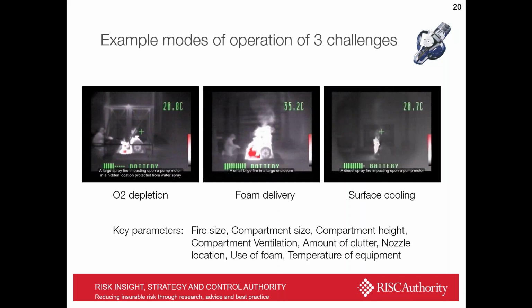But basically, in a very large compartment, this was for a marine application. We designed a system for the military, for the warships. And in this case, in the first video on the left-hand side, that should have been showing you very nicely how hidden fires, that's under a metal table, are tackled. These images are taken with thermal imaging cameras. A very large fire in a completely obscured situation. If the fire is large enough and the compartment is well sealed enough, that fire can be successfully tackled because of inerting of the atmosphere and reducing the oxygen to a point where combustion can no longer be sustained.